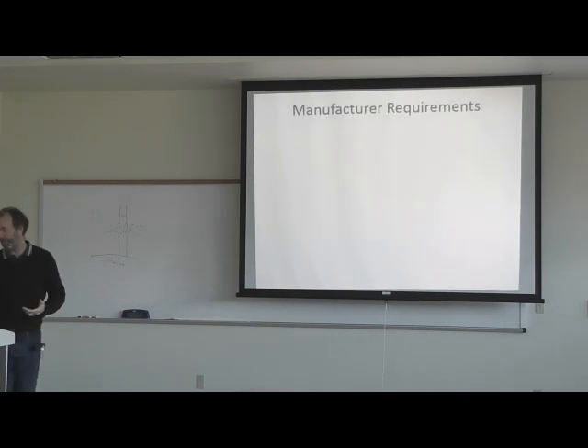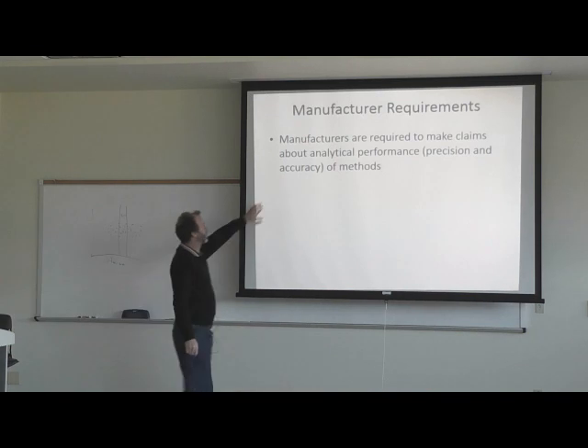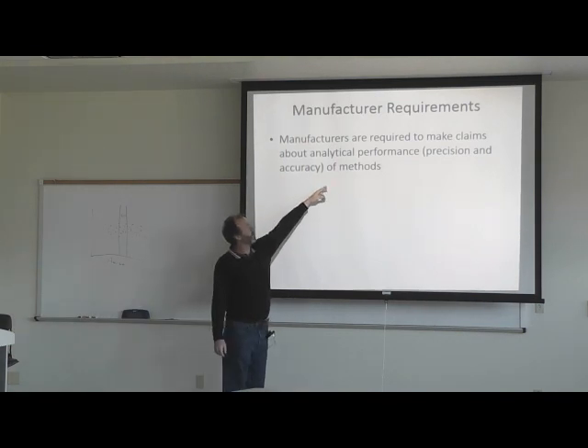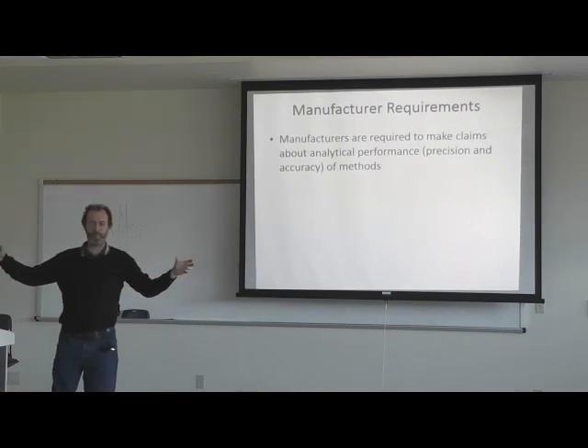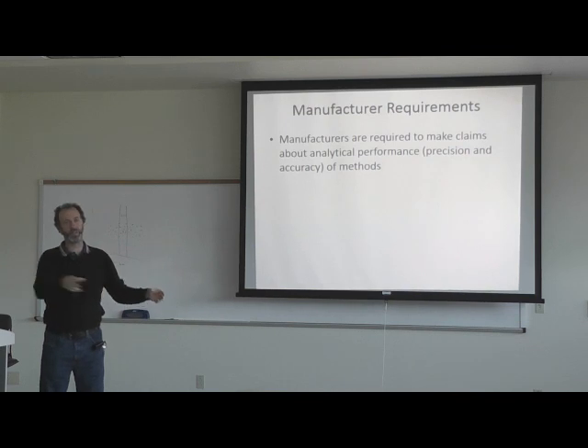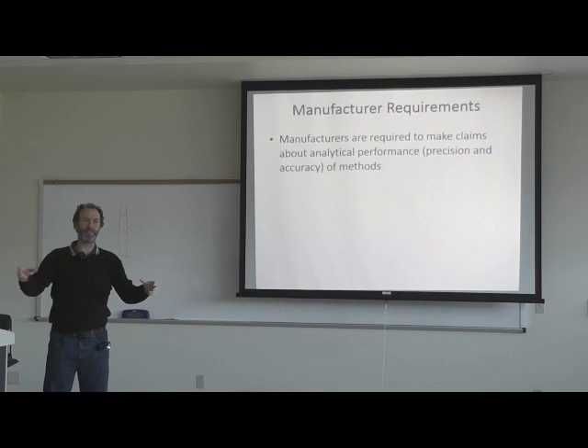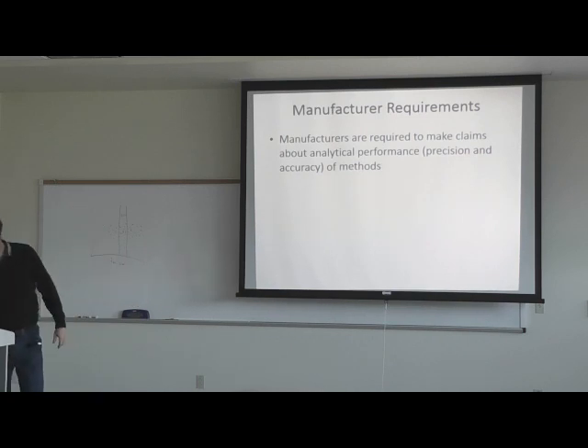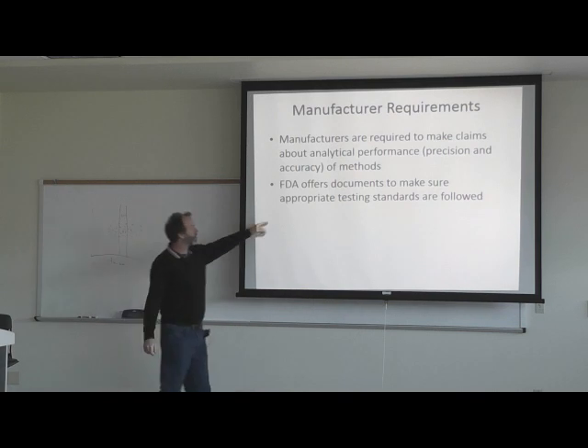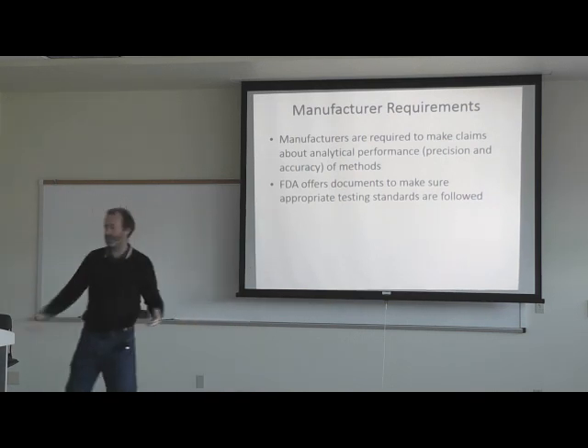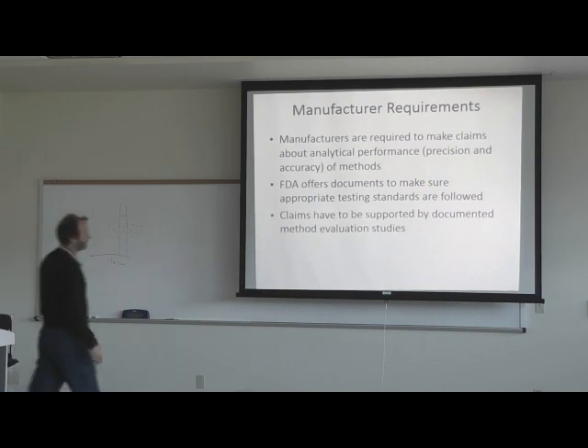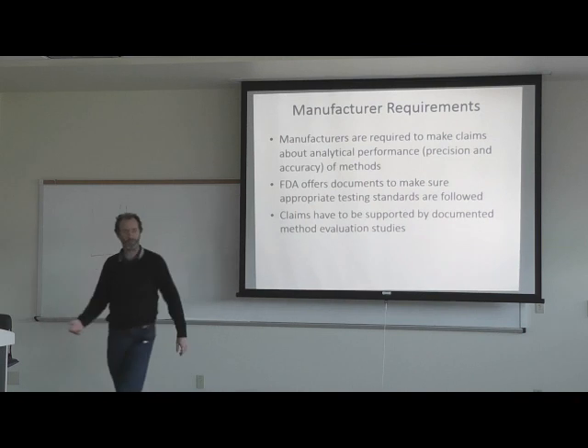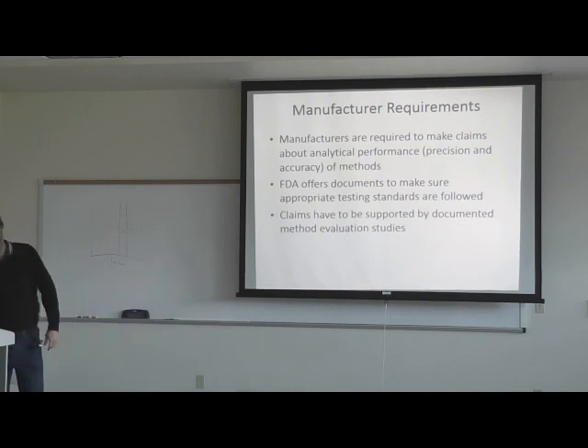Manufacturers of methods are required to make claims about the analytical performance. They do large-scale clinical trials and tell you that this method has this much bias and this much precision. The FDA offers documents to make sure appropriate testing standards are followed. The claims manufacturers make have to be supported by documented method evaluation studies, similar to pharmaceuticals.